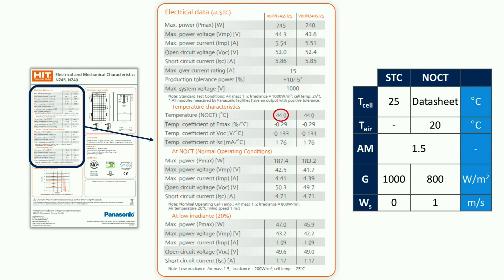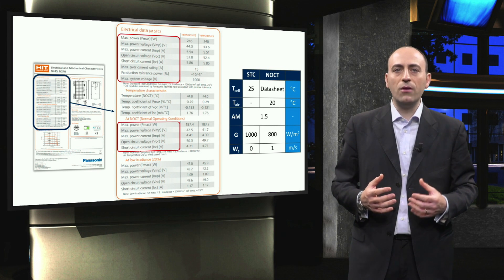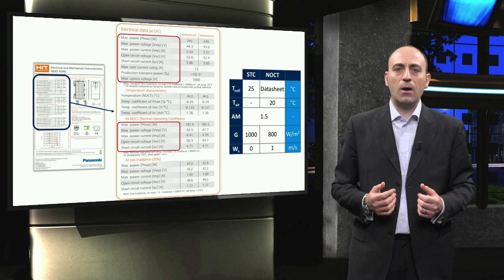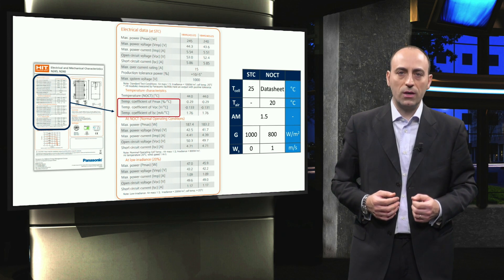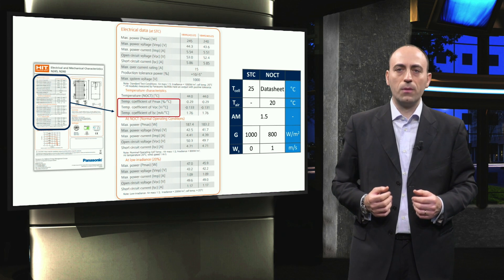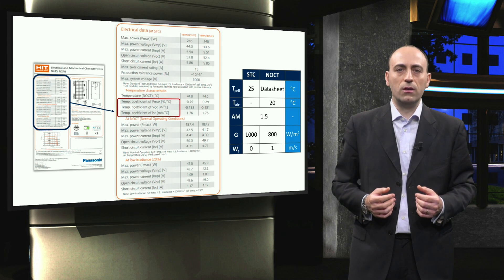Having defined both the STC and NOCT, let's focus on the electrical data of the module: the power, the voltage and the current at the maximum power point, the open-circuit voltage, and the short-circuit current. For the STC, also the maximum current and system voltage are reported for safety reasons, as well as the production tolerance power. This last parameter specifies the range within which the PV module will either overperform or underperform with respect to its rated power at STC. The second table also provides temperature coefficients for the short-circuit current, open-circuit voltage, and maximum power. With these coefficients, the performance of the module can be evaluated when the module operates at temperatures other than the NOCT.